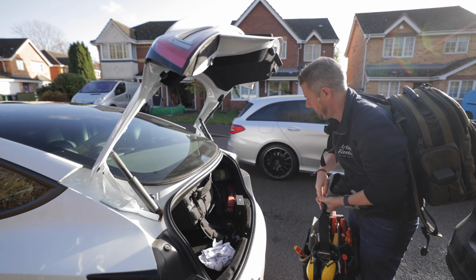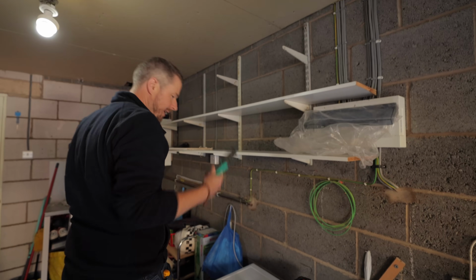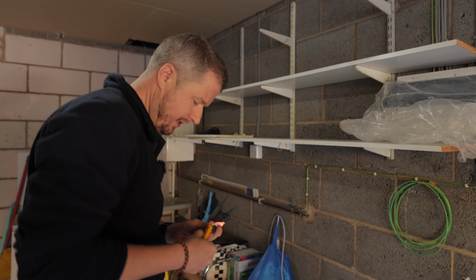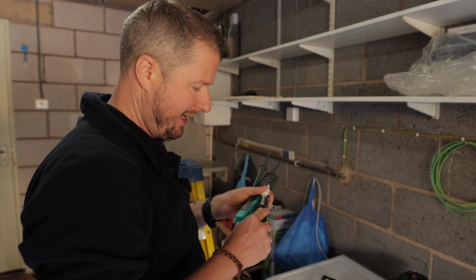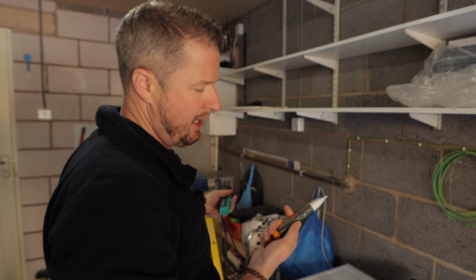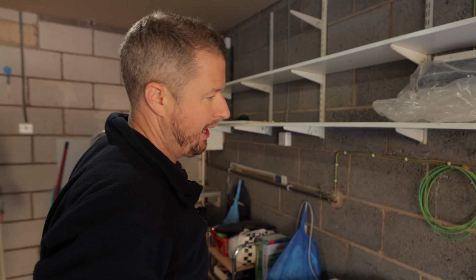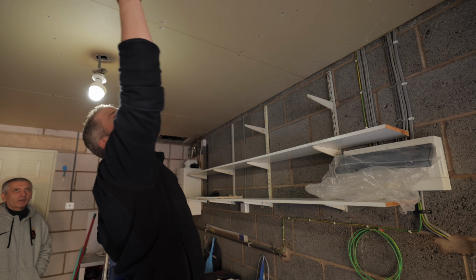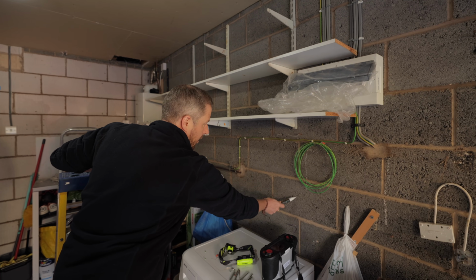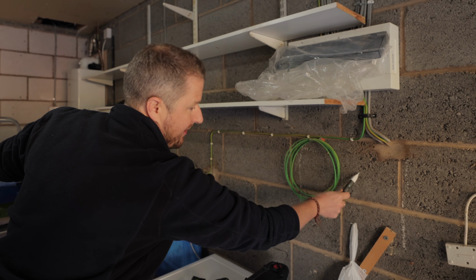So I'm going to get my tester out, and we're going to see what we can find. The first thing I want to do, obviously, is this voltage detector. It's just an indicator, right? So sometimes they can give false readings or something like that. And it's literally everywhere on the ceiling, so that is definitely worrying. You know, if I check this wall, it's okay. Obviously that should be live, that's correct.